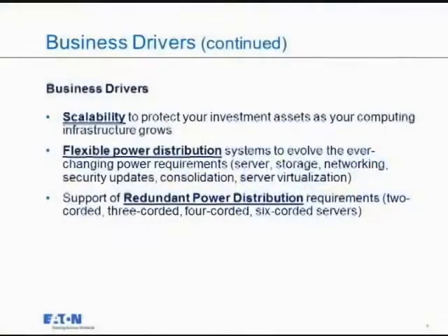Drastically different from an electrical infrastructure perspective, right? I mean, do you have 3-phase power? Do you have single-phase power? All the way down to plugs, number of plugs, expansion. So I said, well, hold the fort. We need to go visit the client to figure out what their ultimate growth and expansion plans are, and what we need to put in place that is both flexible from a power requirement and can grow as they grow, as well as from a distribution standpoint to provide the number of plugs that they may eventually grow into.